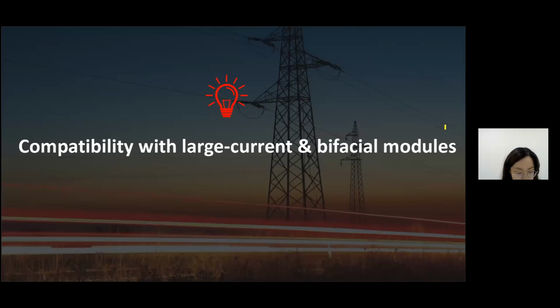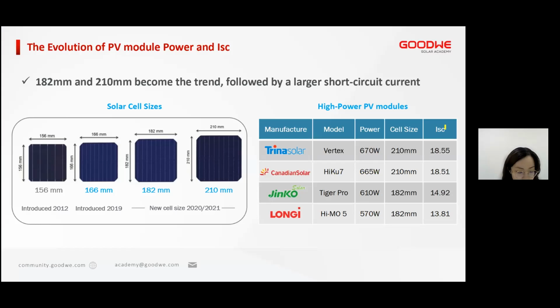Okay, now let's have a look in detail at how GoodWe inverters are compatible with high current and bifacial modules. As we all know, there's an evolution of PV modules with larger sizes and higher power levels. So it brings challenges for the whole PV industry. And for us inverter manufacturers, we need to increase the maximum input current and the maximum short circuit current to be compatible with the mainstream high power PV modules.